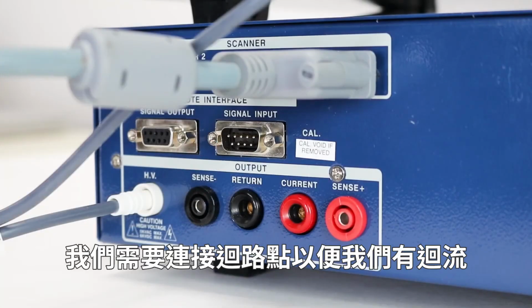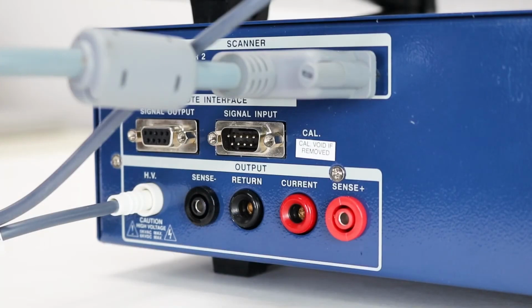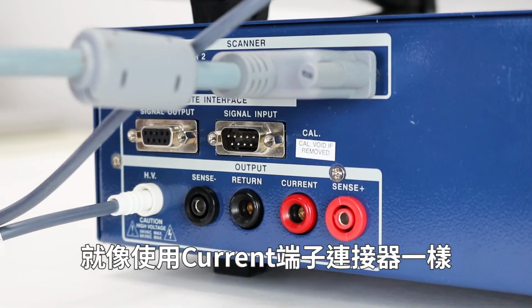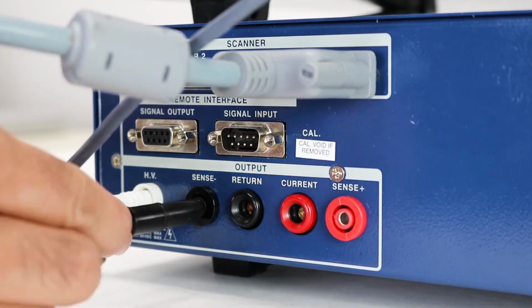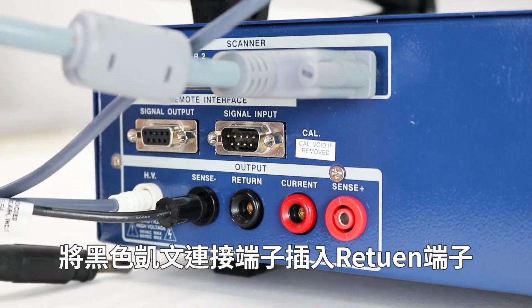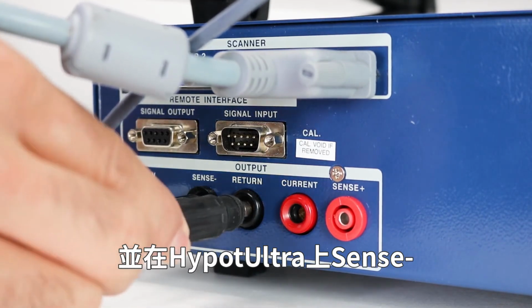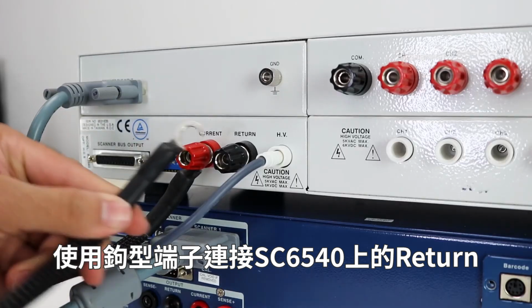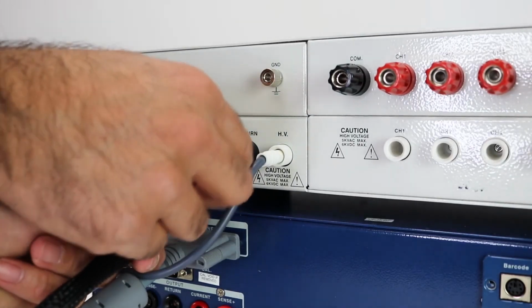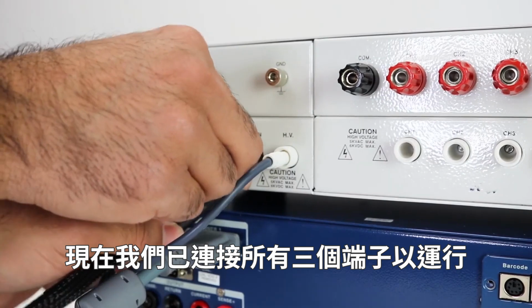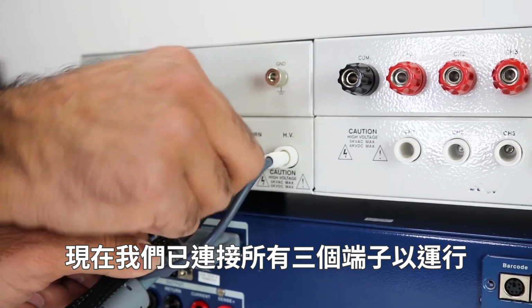Finally, we need to interconnect the return points to allow us a return path for our tests. Just as with the current connector, plug the black Kelvin connector into the return and Sense Minus on the HypotULTRA. Use the hook lug to connect to the return terminal on the SC6540. Now, we have all 3 of our terminals connected to run the test.